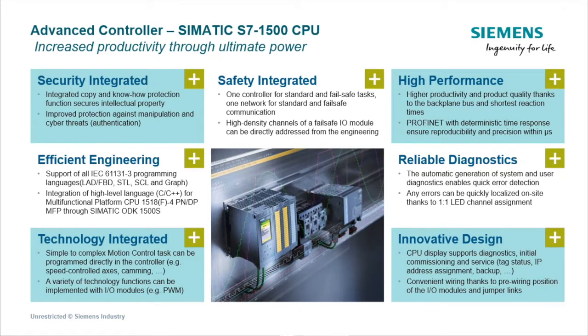Also, the diagnostics is a huge selling point for the S7-1500. The automatic generation of system and user diagnostics allows fast troubleshooting. The system diagnostics are completely built into these CPUs. So when you design your hardware configuration with your CPU, I/O, and everything else, the system diagnostics are already set up. If you have a wire break, which we'll show you in the demo later, or a card disconnect, you automatically get that feedback on your HMI and on your PLC's display. It's a really good diagnostic system and a huge selling point for these controllers.